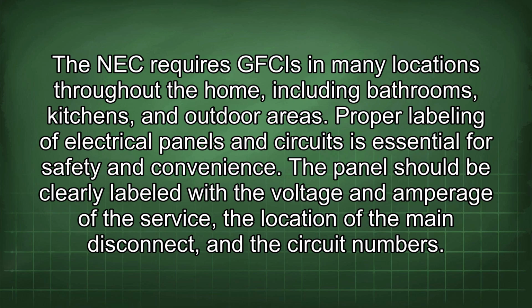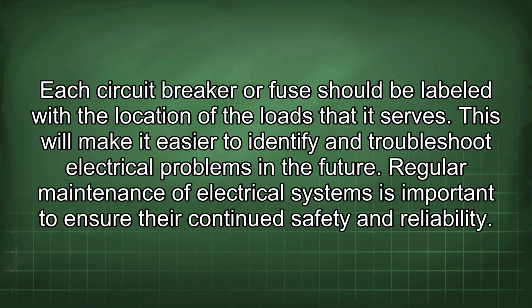Proper labeling of electrical panels and circuits is essential for safety and convenience. The panels should be clearly labeled with the voltage and amperage of the service, the location of the main disconnect, and the circuit numbers. Each circuit breaker or fuse should be labeled with the location of the loads that it serves. This will make it easier to identify and troubleshoot electrical problems in the future.